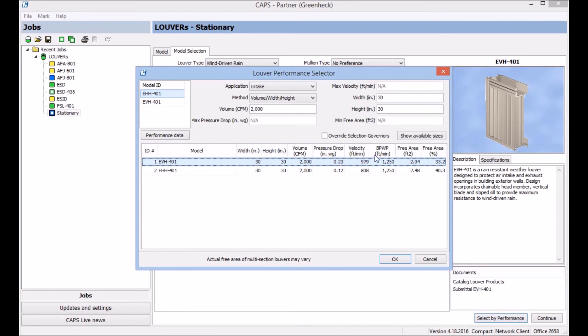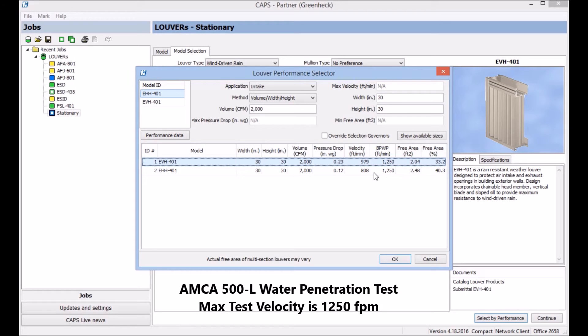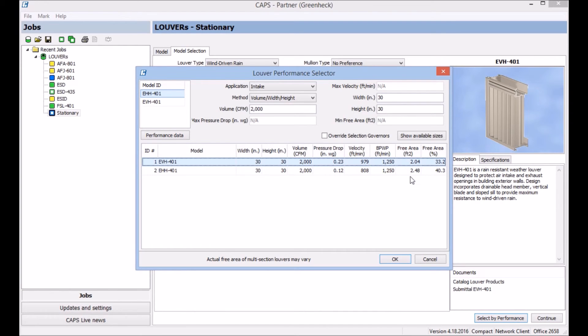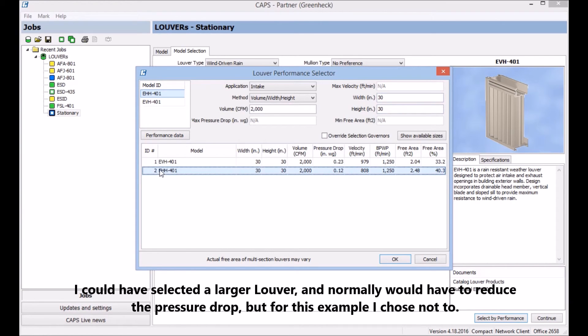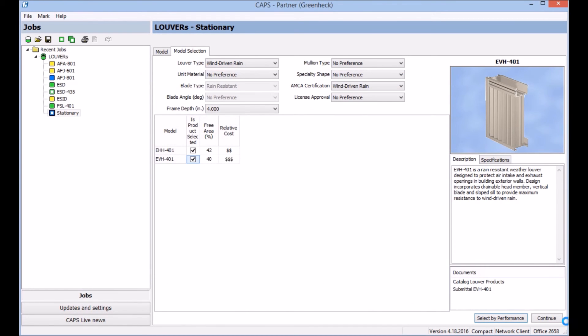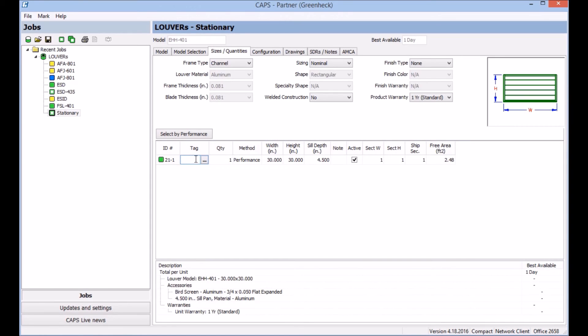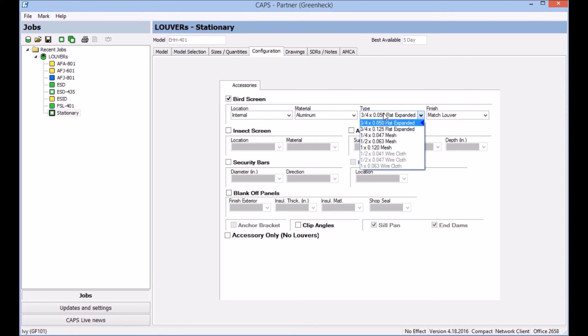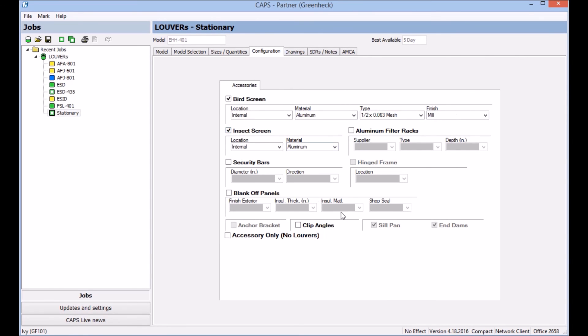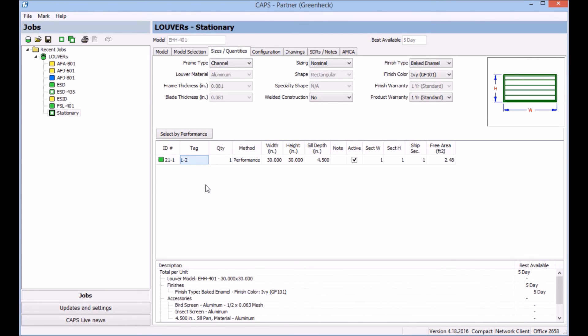The beginning point of water penetration doesn't really matter on these wind-driven rain louvers because they're so effective — that's the max end of that test, which tops out at 1250. My free area is less here, but I don't want any rain to get in there and I also can't afford a quarter-inch pressure drop, and I can't go any bigger due to size constraints. I'm going to go with the horizontal blade louver. Now I can tag it, and again I can select a finish — maybe I'll go baked enamel, ivy color. I can also select bird screen or insect screen. That would conclude the end of our tutorial. Thank you and I hope this was helpful.